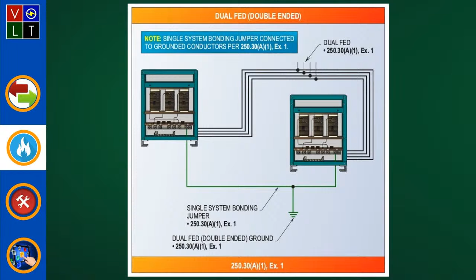It's where you're setting up... We have in our transformer book, and we also have in our design book, where we go in and look at 450.6 and get in where you have transformers and you're creating a bank and you have radial grounds and stuff. That's what this is getting into. Okay. So you would need to size all your conductors off 450, right? No, you still set the system bonding jumper and everything up here per exception one, but 450.6 is where they're talking about these types of transformers where you create these radial grounds. Okay. I was so glad I didn't say 250. David would have to correct me again.